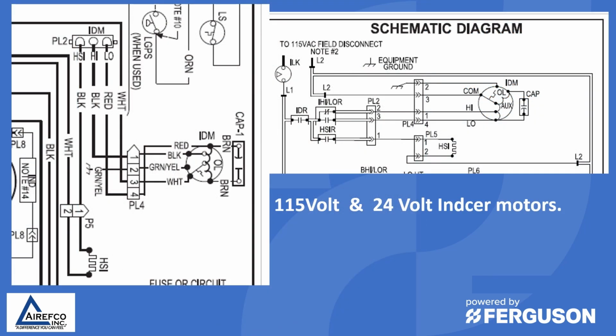So your inducer motors can be different voltages, 115 volts or a 24 volt motor. In this particular wiring schematic, you have a wire coming off L2 to the common and off L1 to the high and the low. And you notice from this diagram that the supply voltage is 115 volts. And so this would be a motor on a two-stage gas furnace, which would run in high and low speed. This could also be a 24-volt circuit, which a lot of your furnaces today run the inducer motor on 24 volts.